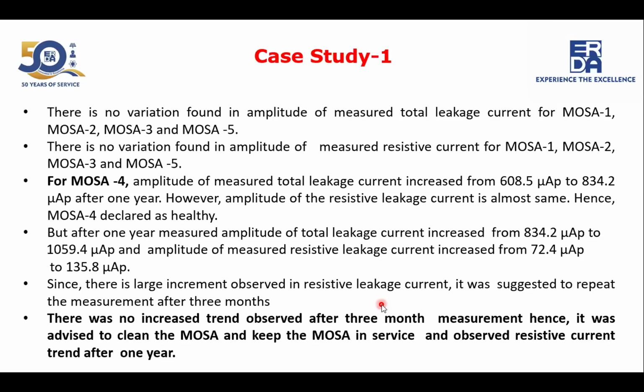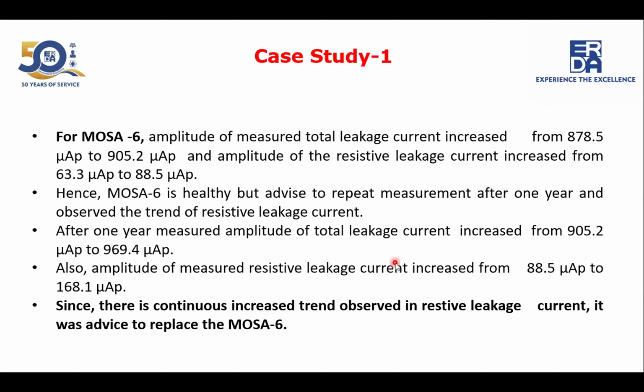After 3 months, there was no increasing trend observed. Hence it was advised to clean the MOSA and keep it in service, observing the resistive current trend after 1 year, because this leakage current may also be due to external contamination. If the surface is externally contaminated, the leakage current may be a little high. So this is one finding.